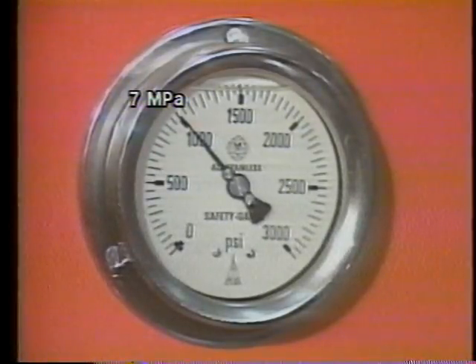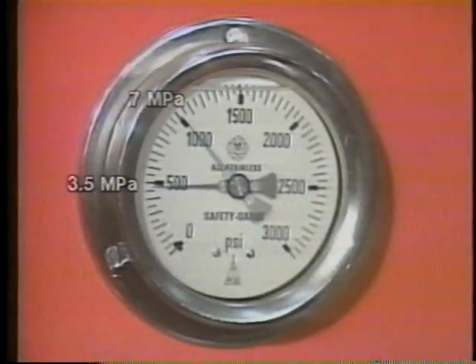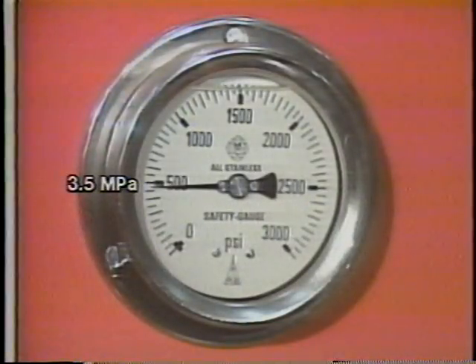If the fluid supply appears good, the reading on the pressure gauge is normal, and you have discovered no unusual noise, you can assume the pump is operating correctly. But suppose system pressure is abnormally low — this indicates there is a leak or a break somewhere in the system, or that a passage is open to the tank. Somehow fluid is escaping from the pressure side of the circuit.